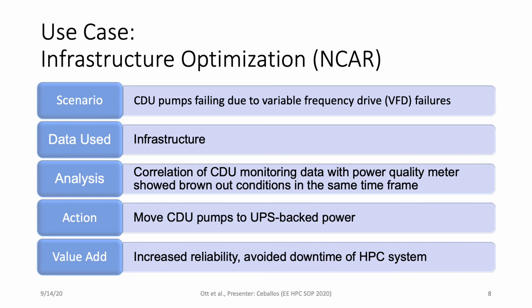Through integrated data analysis, they were able to correlate site-wide power quality issues with VFD failures. The NWSC staff then transitioned the CDU power from the direct utility to UPS-backed power. This enhancement gave the CDUs clean power, so they were no longer exposed to the brownout conditions as before.